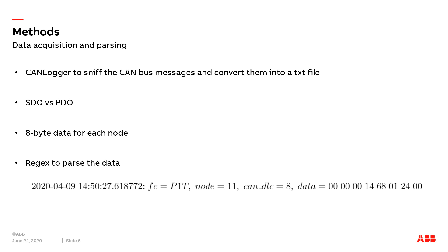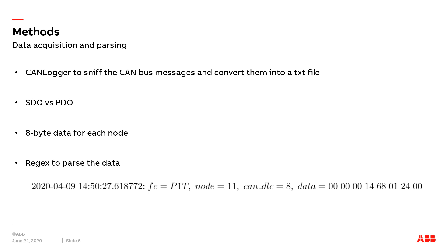The SDO communication has a restriction that it can only allow accessing one object dictionary at a time, which can cause a lot of overhead for accessing data that changes continuously. The PDO protocol is used for processing real-time data in various nodes such as sensors and voltage meters, which is more suitable for our situation. The data transferred by PDO is 8 bytes for each node at the time point.